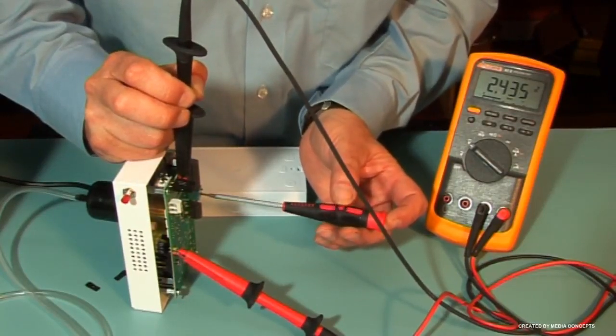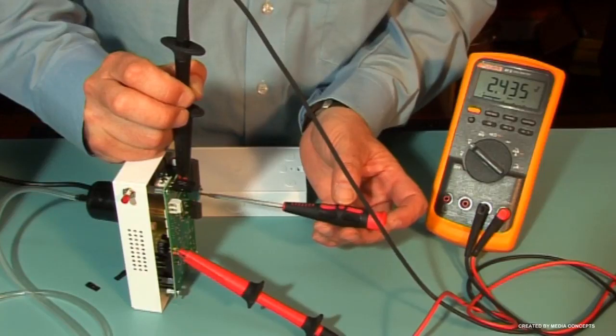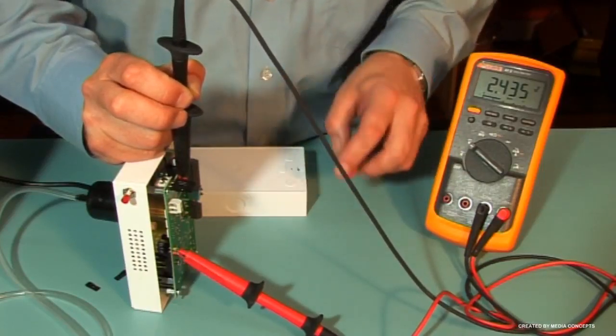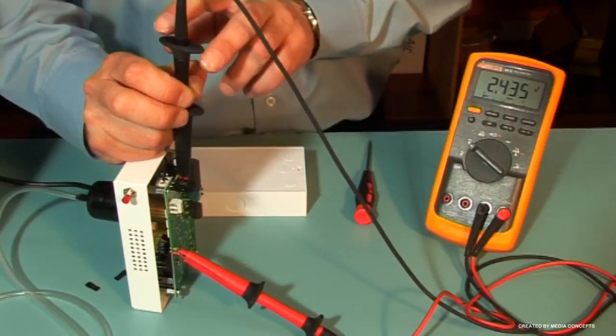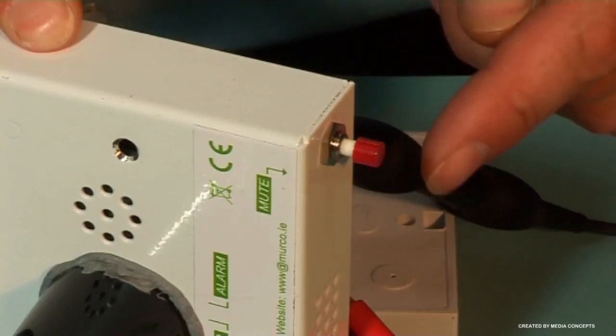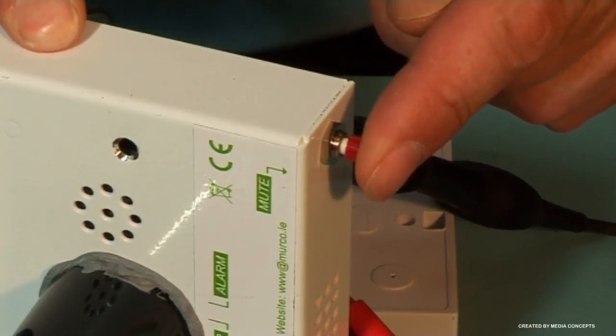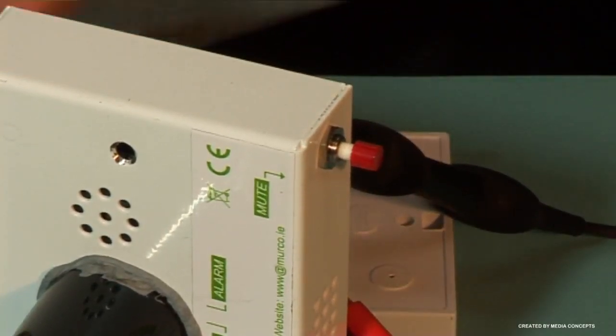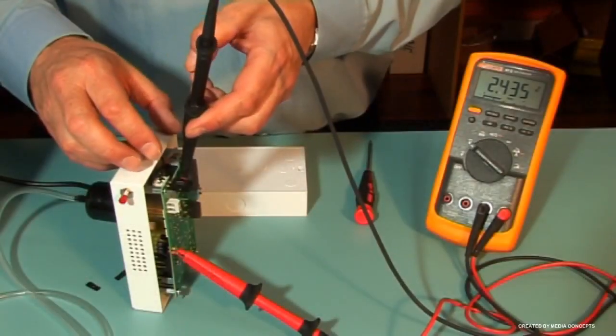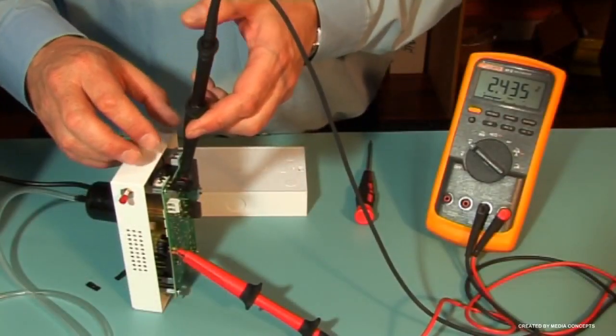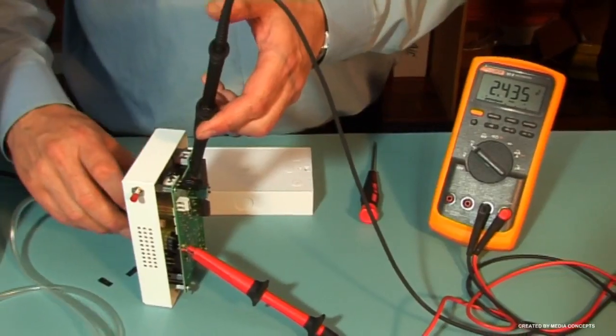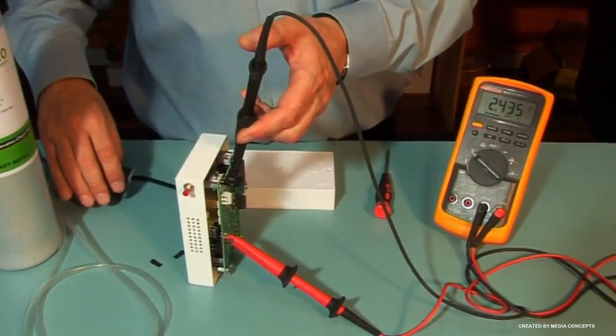The IAM will now be in alarm and relays should activate, and if the IAM is connected to the remote IAM-C panel, then the red LED on the IAM-C should be lit. The IAM sounder can be silenced using the red mute button. Remove the gas and the unit will come out of alarm and return to its normal voltage of 0.3 volts, or as the settings on the rating label.